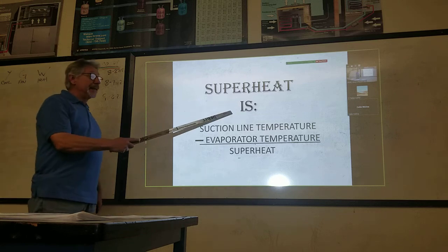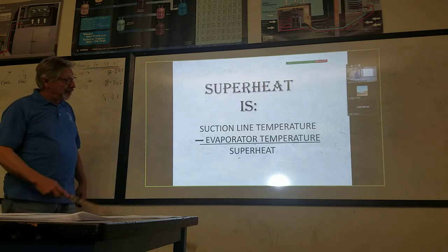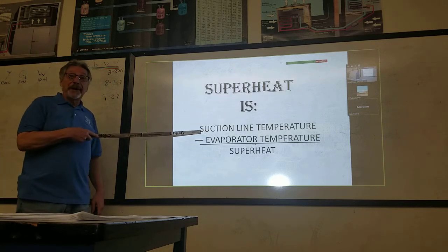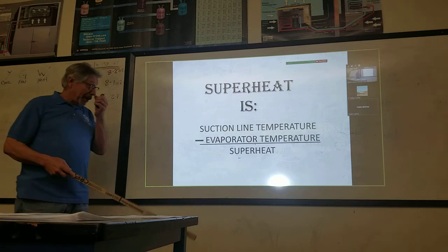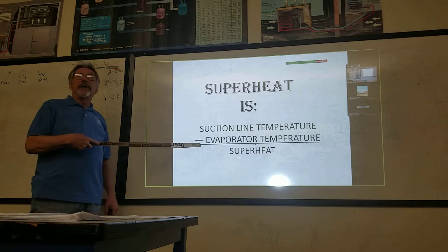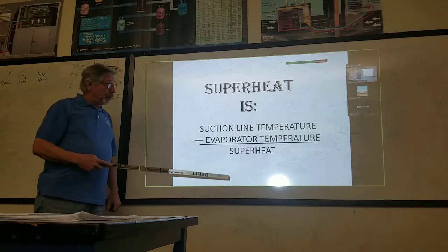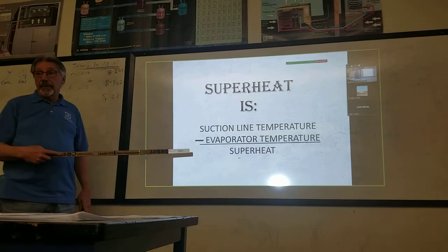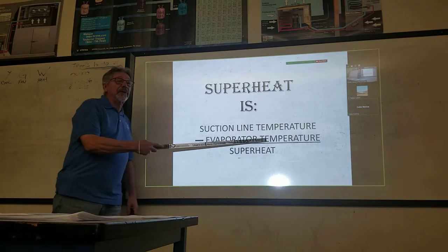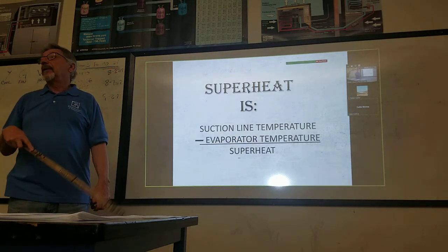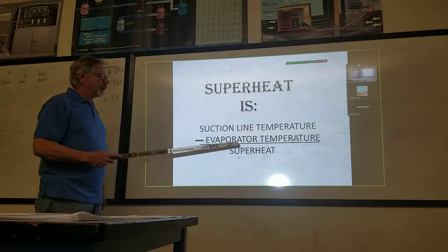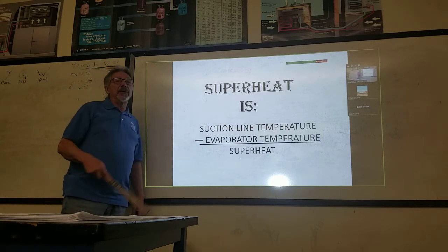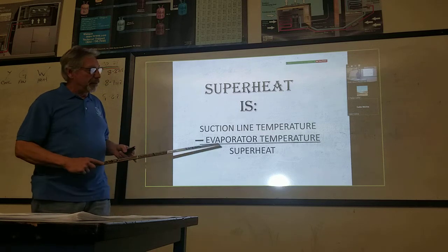Okay, superheat is Superman. Suction line temperature minus the evaporator temperature, or the saturation temperature. The surface temperature of the evaporator is pretty much the saturation temperature of that refrigerant. So we're gonna take a temperature on that line.